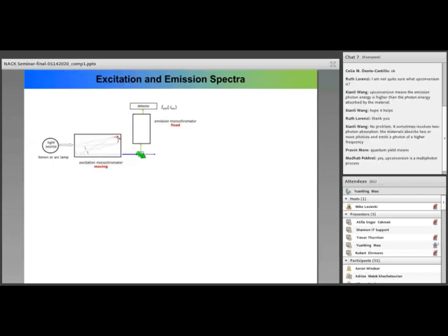You see this configuration is at 90 degrees between the excitation monochromator and the emission monochromator. It's very useful especially for the powder samples, which we normally work with, because they are not transparent, so we use reflected light to do this measurement.